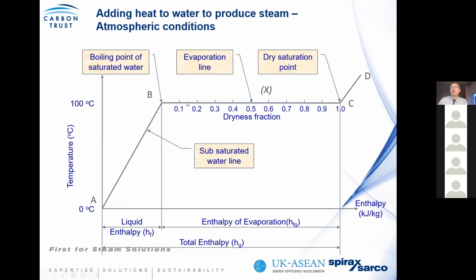We then start adding additional energy, and as we slide across this dryness fraction scale, the more energy we add, we'll come to a point where we create what's called dry saturated steam with a unity dryness fraction, or fraction of 1. If we generate steam with a reduced dryness fraction, say for example 0.9, what that means is that we have only 0.9 times the available enthalpy of evaporation, because 10% per volume is still water. So it's important that when we're considering steam to end users, we consider the dryness fraction, because this has a significant and often unrecognized consequence for steam quality, steam efficiency and reliability of plant.